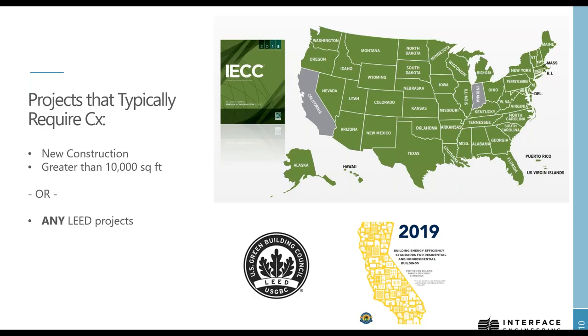So let's get started on why commissioning is not optional, at least from the point of view of code requirements. At this point in time, as you can see from the map that we've got up here, the majority of the country right now is following the 2018 IECC. And as part of IECC, pretty much any new construction that's greater than 10,000 square feet is going to require some amount of commissioning. California, not included in this nice big green map, has their own that's even more stringent on the energy code side, that once again still includes commissioning as well.